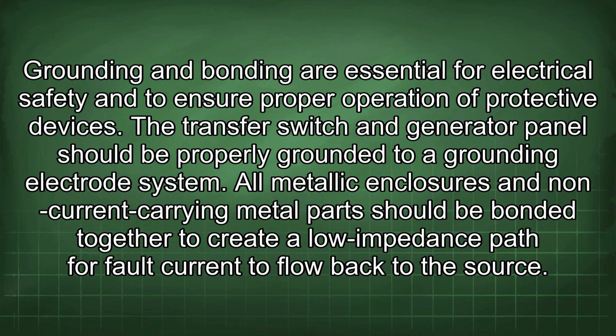Grounding and bonding are essential for electrical safety and to ensure proper operation of protective devices. The transfer switch and generator panel should be properly grounded to a grounding electrode system. All metallic enclosures and non-current carrying metal parts should be bonded together to create a low impedance path for fault current to flow back to the source.